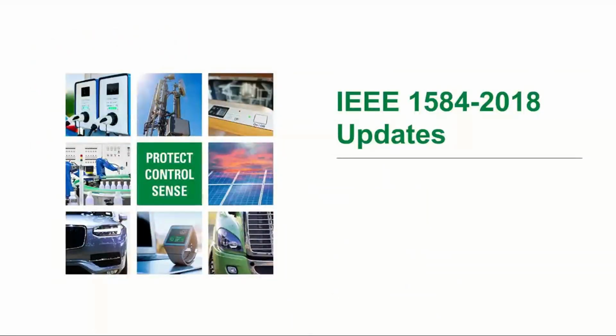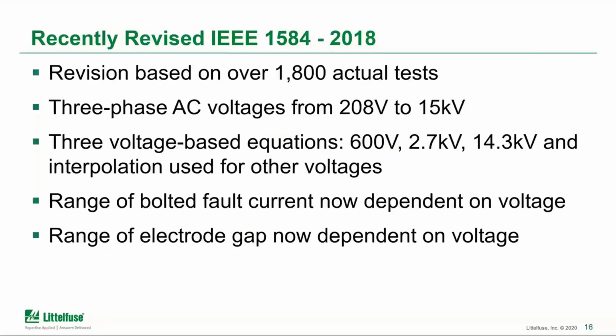Okay, so moving on to the IEEE 1584 standard itself, I want to highlight a few of the changes. Again, this is certainly not a comprehensive review, but a few highlights that would be interesting. With the 2018 version, the new data was based on a whole battery of additional testing. Here it shows over 1,800 tests that were performed, and the formulas apply to systems from 208 volts up to 15 kV. There are three different equations provided by IEEE 1584, built at 600 volts, 2.7 kV, and 14.3 kV, and then interpolation is used to build the numbers for the other voltages.